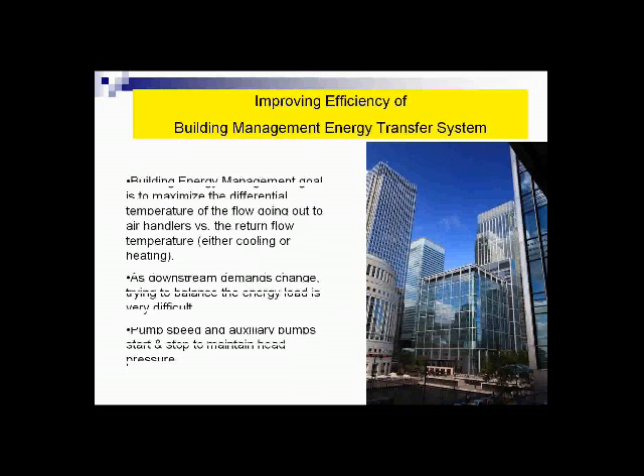The goal of a building energy management team is to try to maximize the differential temperature of the flow going out to an air handler versus the return flow temperature. And this is true of either heating or cooling. As an example, if you come out of your chillers and you're sending 50-degree chilled water out to a building to cool it, you would want that return water temperature to be in the 70-degree range. You want the most differential temperature you can get, the better it is.